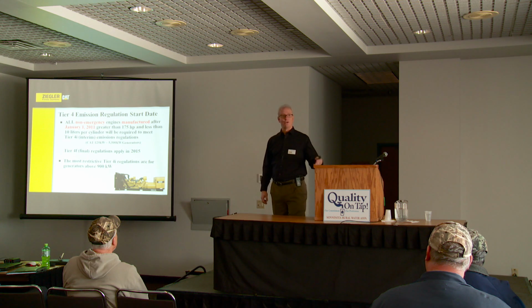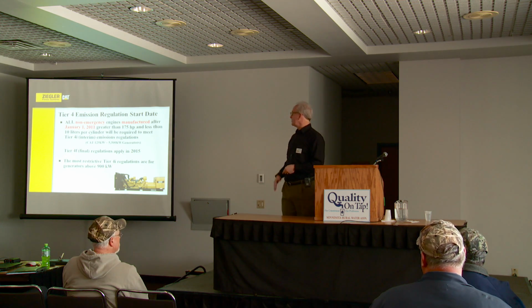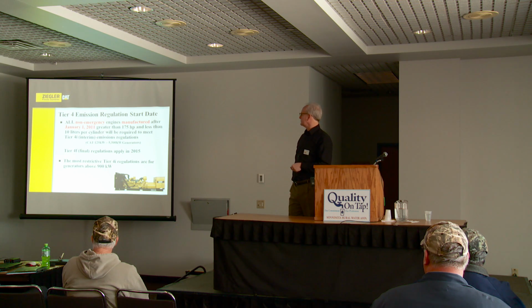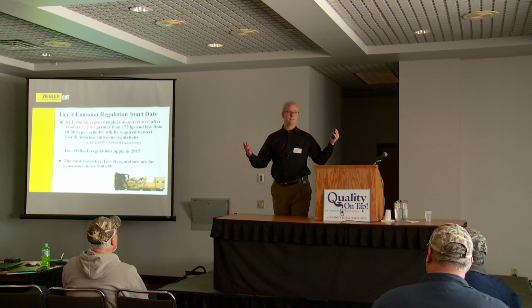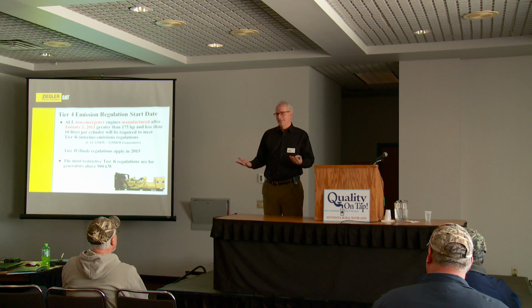So as I said, Tier 4 is the place where the rules came out, those bands where you have to decide about, is it emergency or non-emergency. And so in medium-big and big engines, it says that non-emergency engines manufactured after January 1st, 2011, greater than 175 horsepower, must meet Tier 4 emission levels. And that's non-emergency, so if you're an emergency generator, that's fine, you don't have to. And again, if it was manufactured some other time, there's also another set of rules. I'm not sure why the EPA didn't have Tier 4 and then Tier 5, but no, they have Tier 4 interim and Tier 4 final. I don't know, it makes sense.